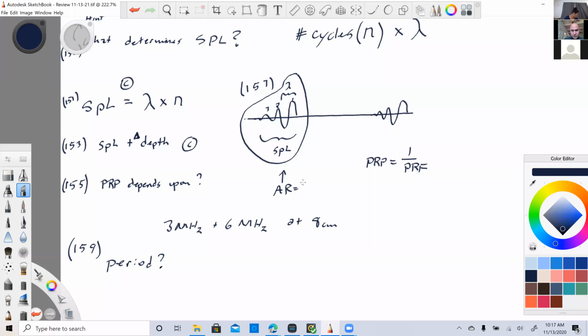Axial resolution is equal to 1/2 the spatial pulse length. But axial resolution does not change no matter what your depth is. Your lateral resolution changes, your slice thickness changes somewhat, but lateral resolution definitely changes. Axial resolution does not change because your spatial pulse length does not change. This length, the time in between, that does change.